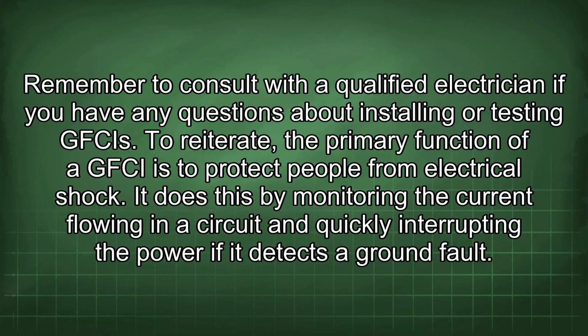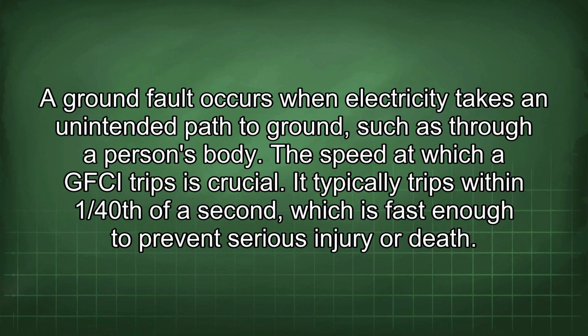To reiterate, the primary function of a GFCI is to protect people from electrical shock. It does this by monitoring the current flowing in a circuit and quickly interrupting the power if it detects a ground fault. A ground fault occurs when electricity takes an unintended path to ground, such as through a person's body. The speed at which a GFCI trips is crucial. It typically trips within 1/40th of a second, which is fast enough to prevent serious injury or death.